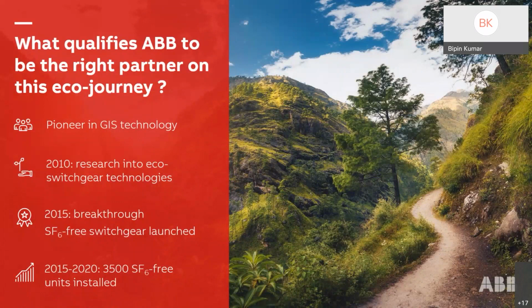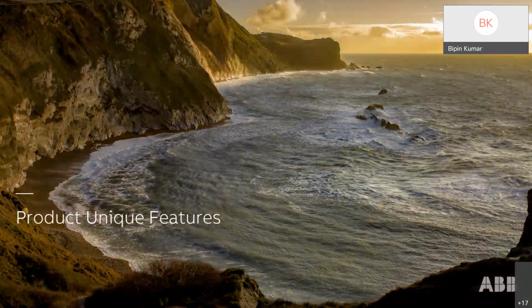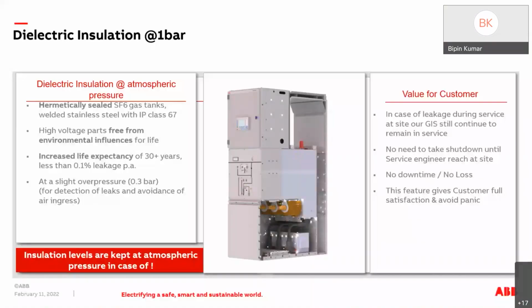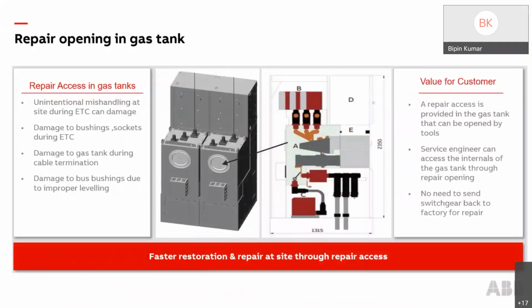Yeah, so we've been trying to develop, as I said, an alternative to SF6 gas, and we have been working on it for the last decade now. And thereafter, we have come to fluoroketones, and then we have come to dry air. So a lot of things we are doing, and we have installations across the globe. It is also designed for dielectric insulation at 1 bar, because our GIS are designed so that even if the SF6 leaks, you need not switch off the GIS. The GIS is very much capable of running at 1 bar pressure. That has been a feature of our gas insulated switchgear as a whole.